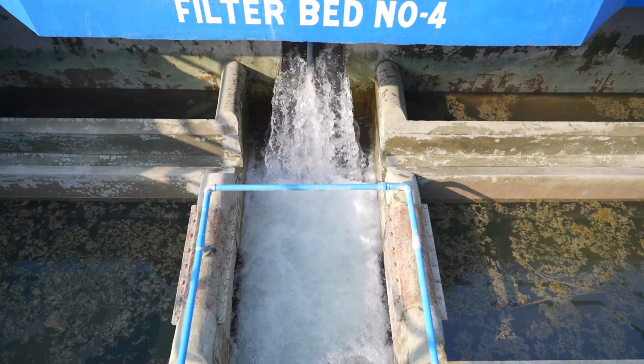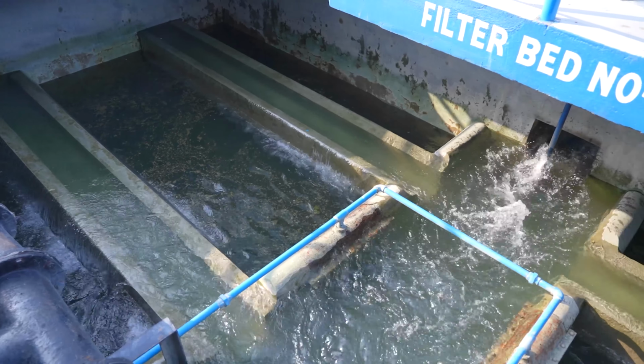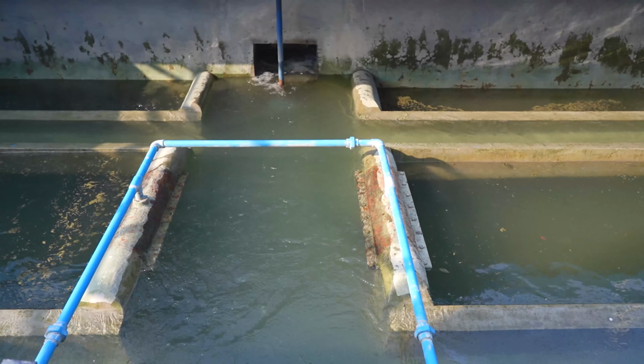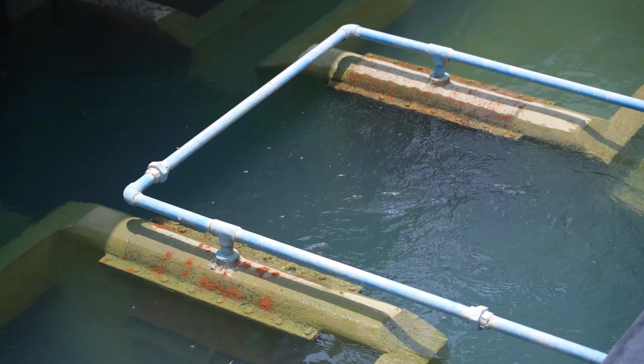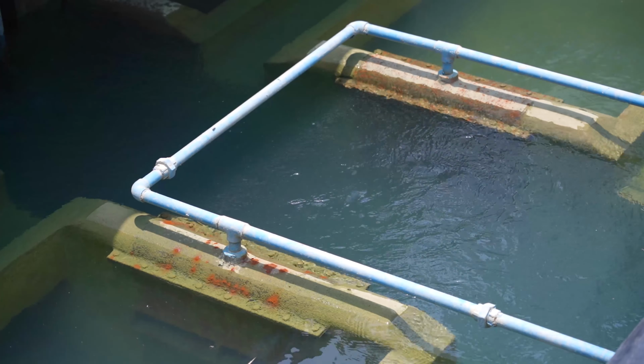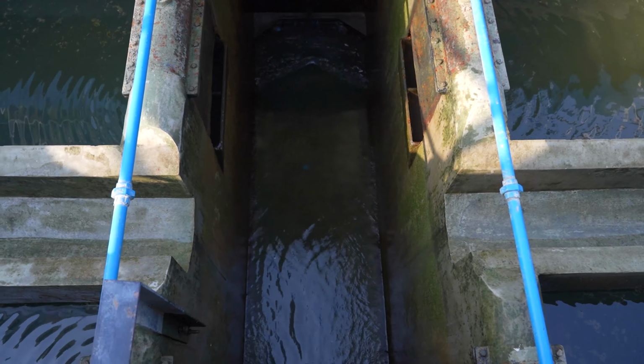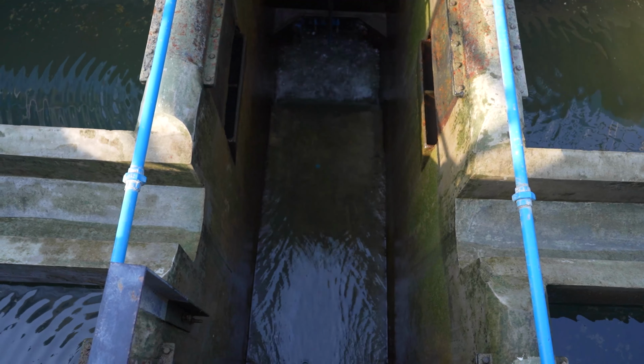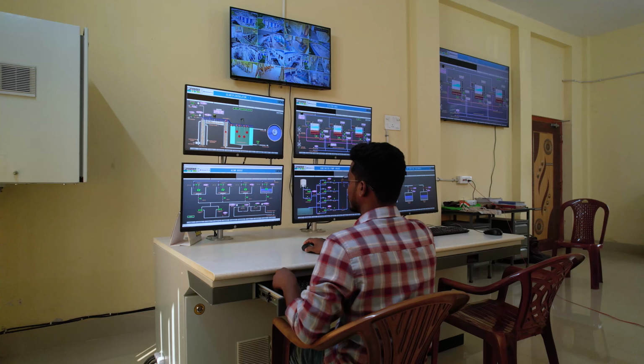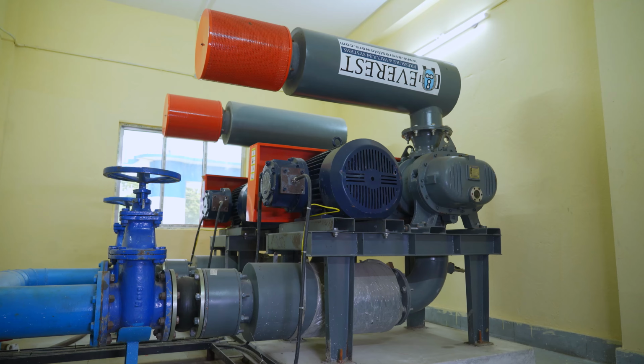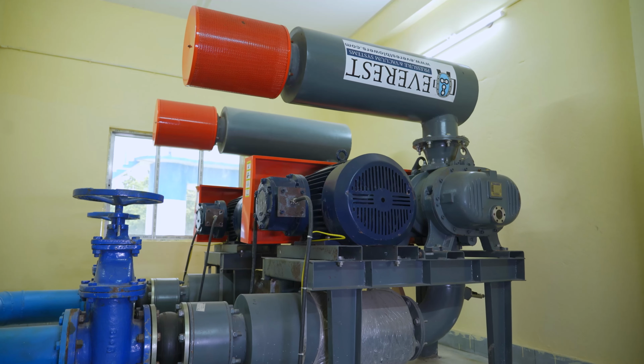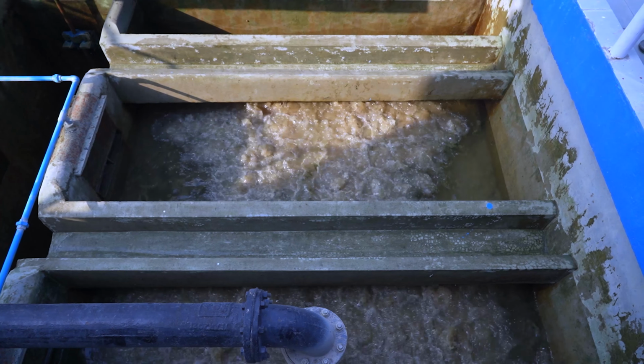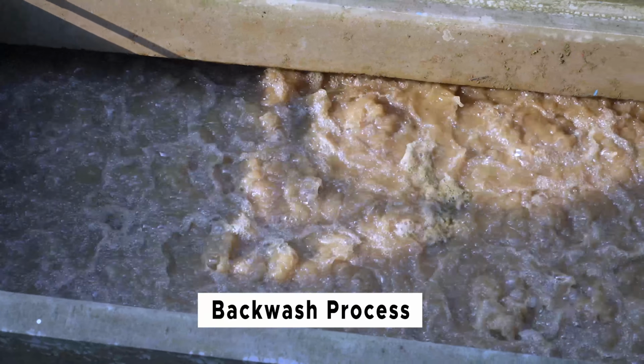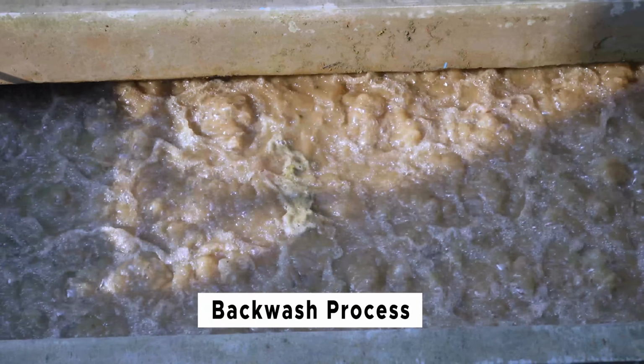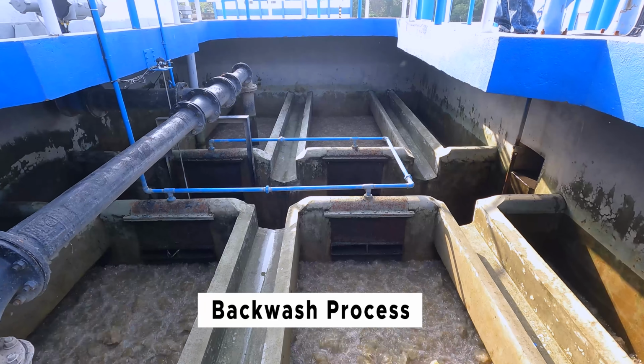The backwash process starts with closing of the input gate valve, followed by closing of the output valve. If the water level is high, then by opening the waste outlet valve, it is reduced to low. Then the valve of the air purging channel opens. After that, the air blower starts. Air from the blower passes through the bed and loosens it. The blowing of air continues for a while, then it stops.